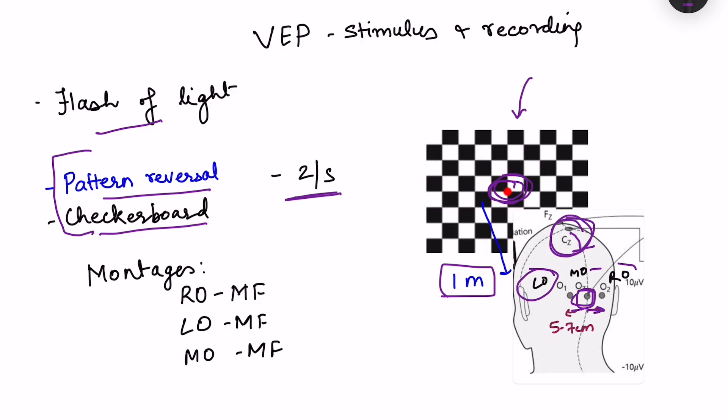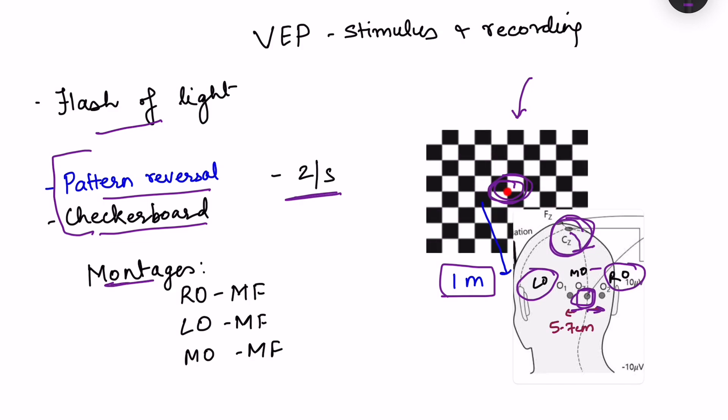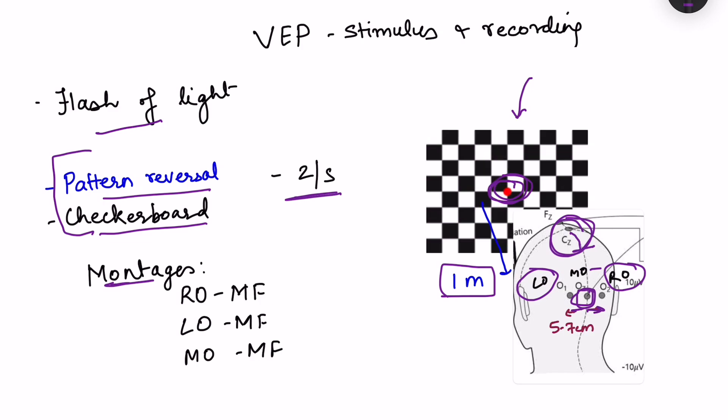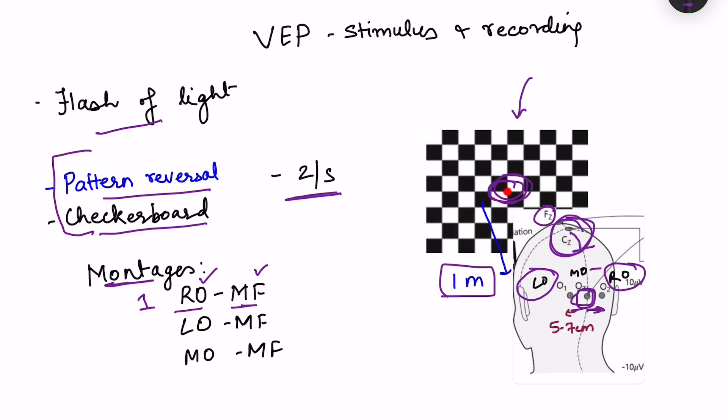So we have left occipital recording, right occipital recording, and then we create montages. Montages is basically the combination of the electrodes which are recorded. So right occipital with mid frontal, that is frontal is the FZ electrode. This FZ electrode is placed in the frontal region. So we see the potential difference recording between the right occipital electrode and the mid frontal electrode. This is known as one montage. Then we see the potential difference between the left occipital electrode and MF electrode, mid frontal electrode. And then third montage is midline occipital, that is the OZ electrode and the mid frontal electrode. So with the stimulation, EEG recording is seen in these three montages.